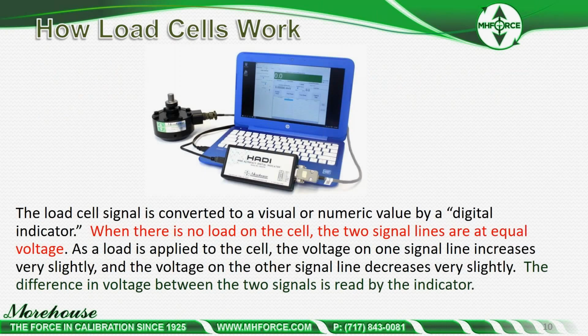So how do load cells work? The importance of learning about strain gauges is really to determine how load cells work, because we're going to troubleshoot them. So a load cell signal is converted to a visual or numeric value by a digital indicator. When there is no load on the cell, the 2 signal lines are at equal voltage. As the load is applied to the cell, the voltage on one signal line increases very slightly, and the voltage on the other signal line decreases very slightly. The difference in voltage between the 2 signals is read by the indicator. This is where you typically will get your millivolt per volt, if you're using a HADI, a DSC, an Agilent, or some of the other ones.